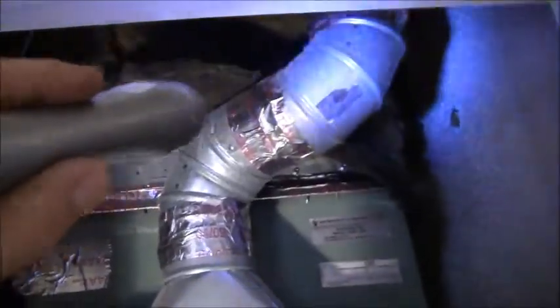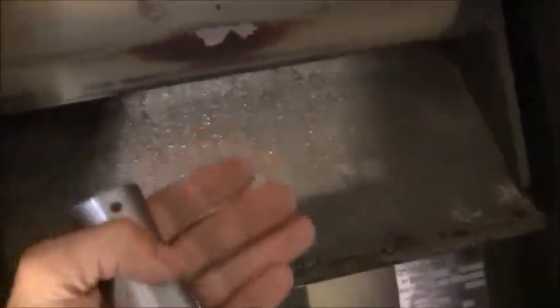So in case there's a pressure inside of the venting of the products of combustion, it will come down and roll out this way here to prevent the flame from being disturbed. So this is how the draft diverter works on this furnace, okay? That's why you don't have a gap like a hot water heater. You have a gap right there, but on this one you don't have the gap because the draft diverter is down at this location. So that's how the manufacturer did that, and that's very common for this 80% furnace.